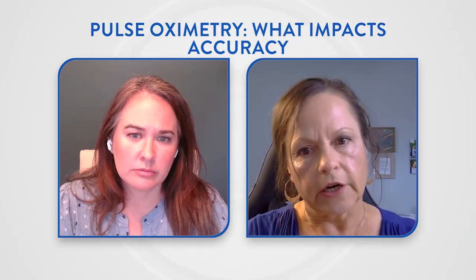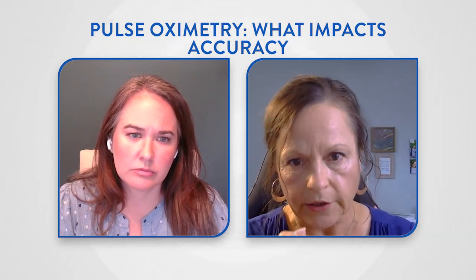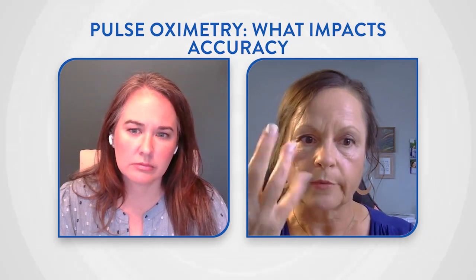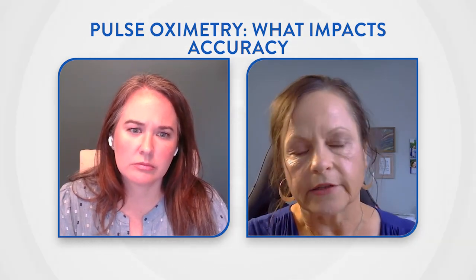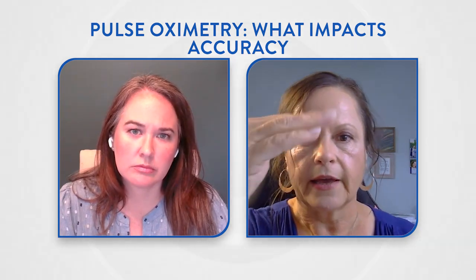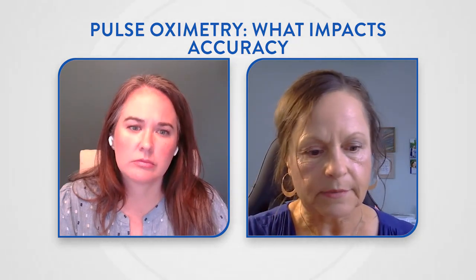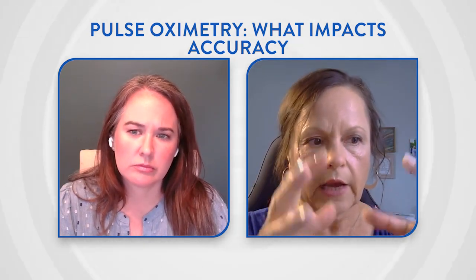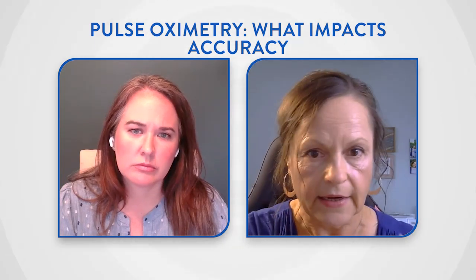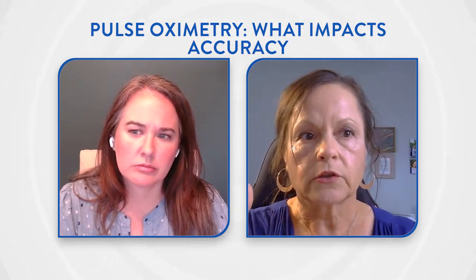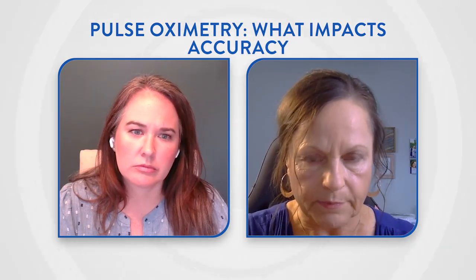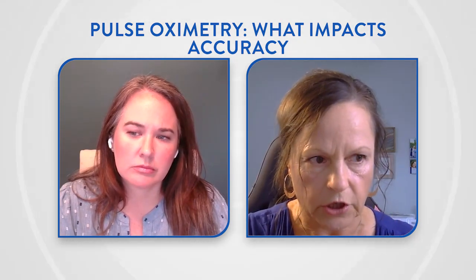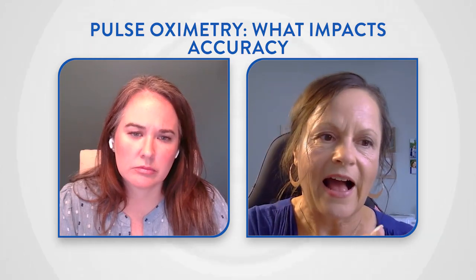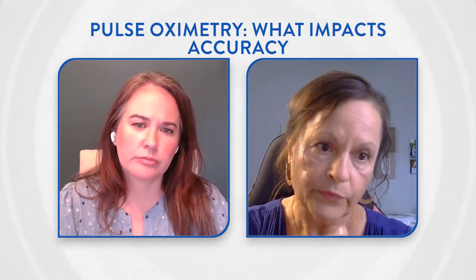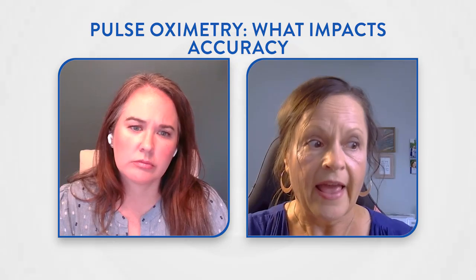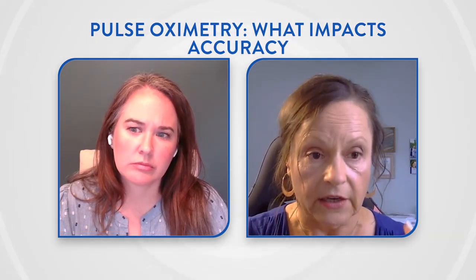However, you put a darker skin on there that absorbs more color than light colored skin, because dark absorbs more than white. What's happening is you're getting a false high, because all that device is meant to do is count color and create a ratio. That's it. It has nothing to do with actual oxygen. So it perceives that more light is being absorbed because of the darker skin, and it's reflecting a higher O2 saturation rate than what the patient of color may actually have. That's a big deal.